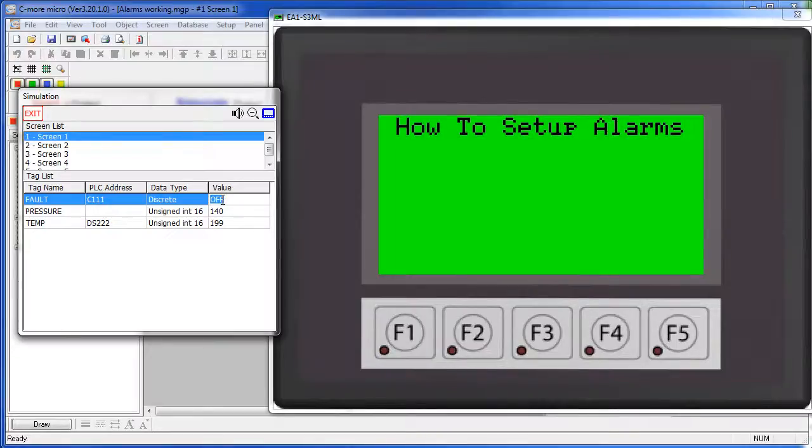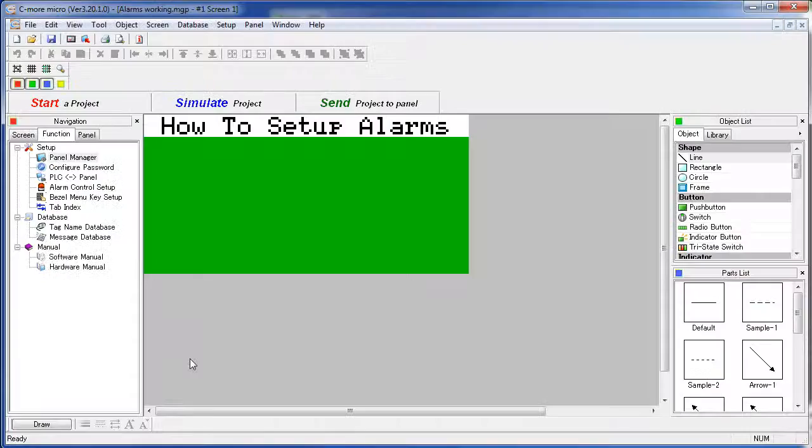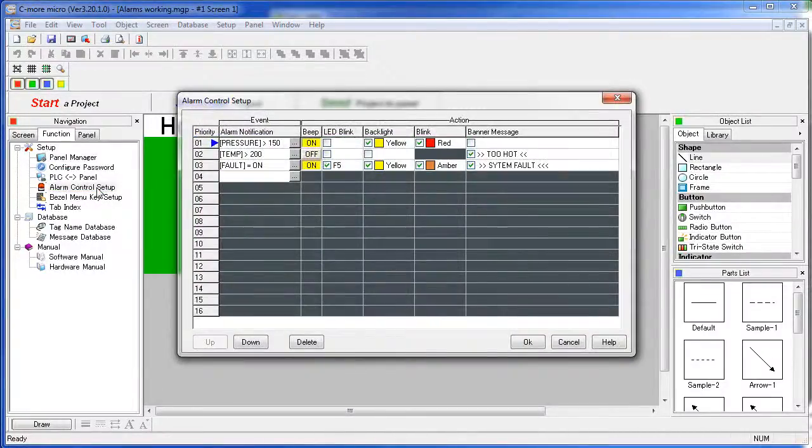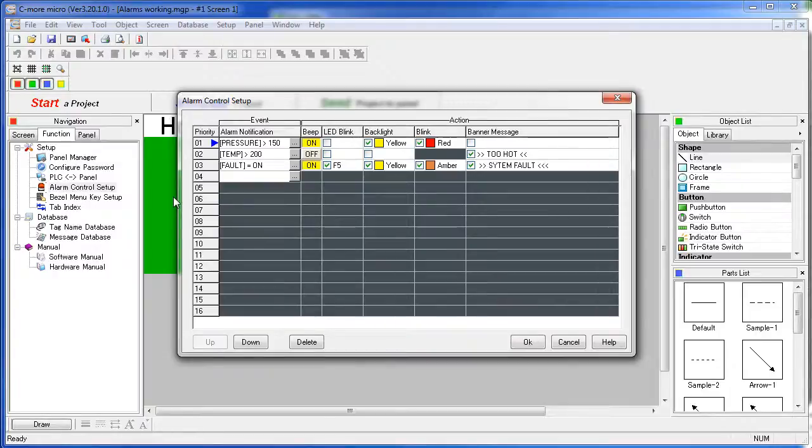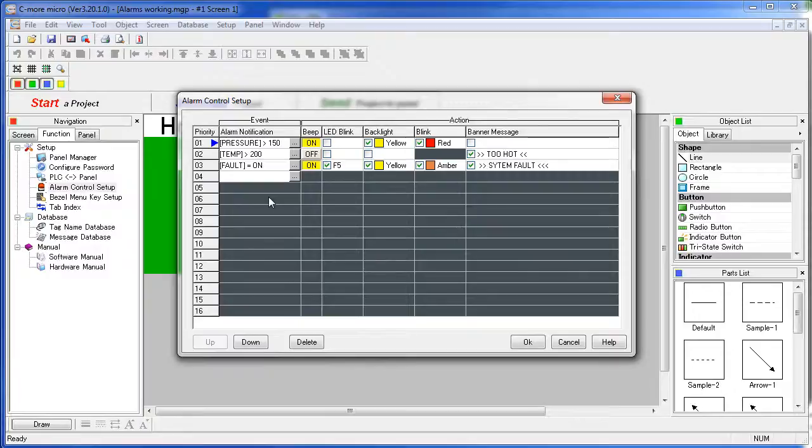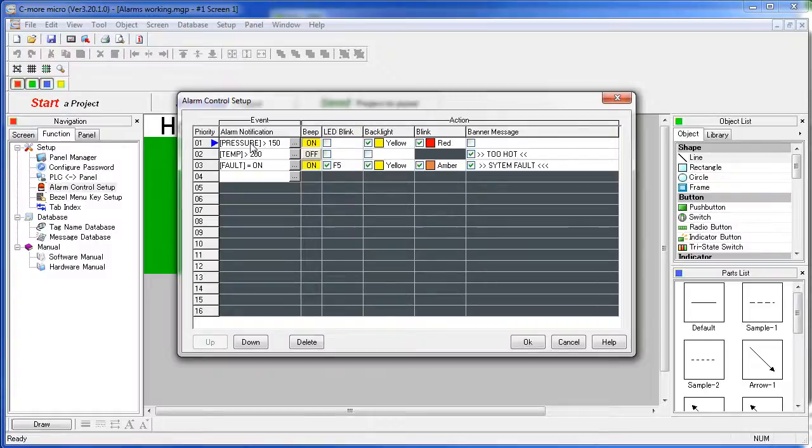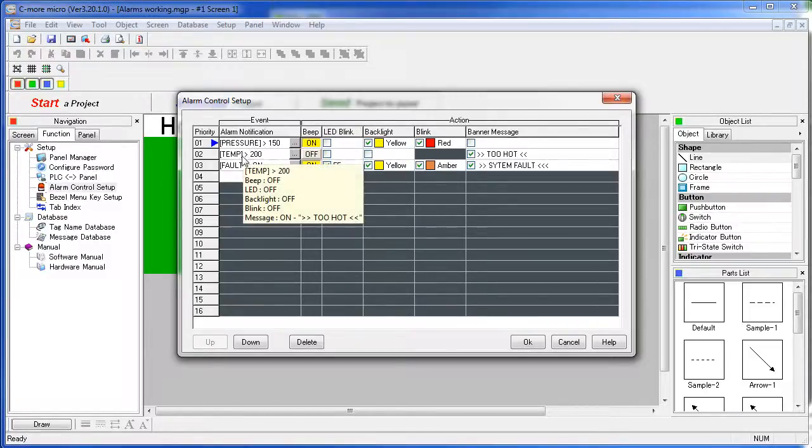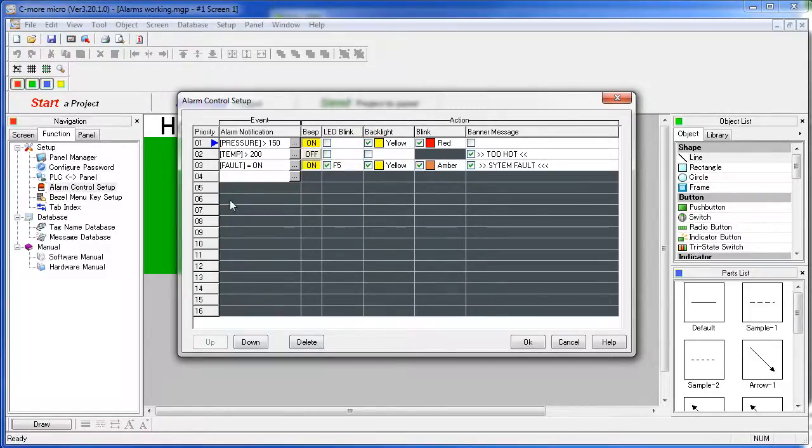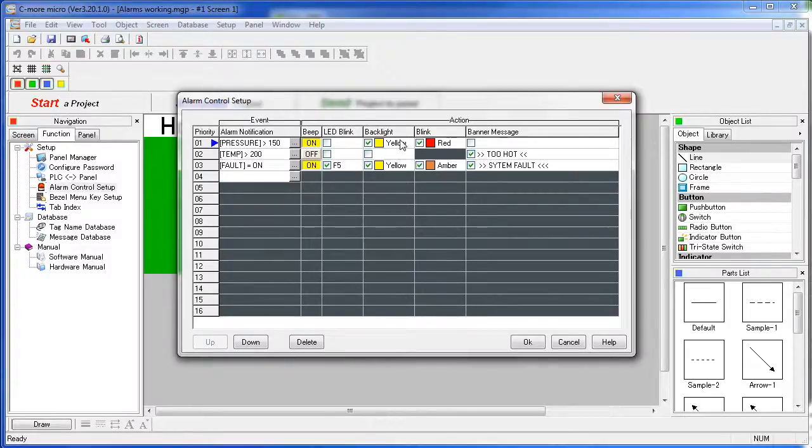One final note on alarm priority – let's go back to our alarm setup screen and take a look at this. If multiple alarms are active at the same time, the highest priority alarm will be issued. The alarms are shown in this dialog in priority order. You can see this is the highest priority alarm, this is the next priority, this is the next priority. You are allowed to set up 16 alarms and the top one in this list will be your highest priority alarm.